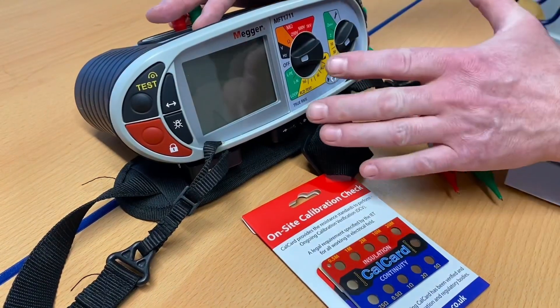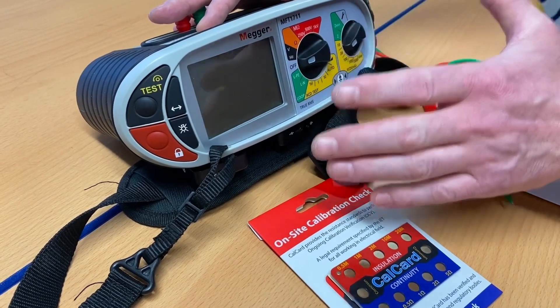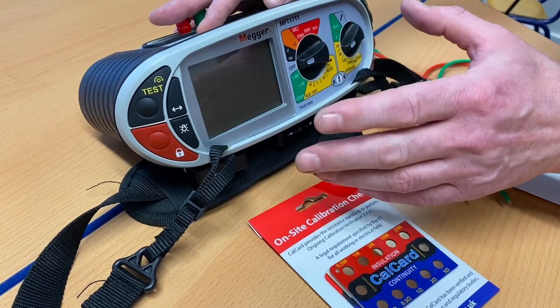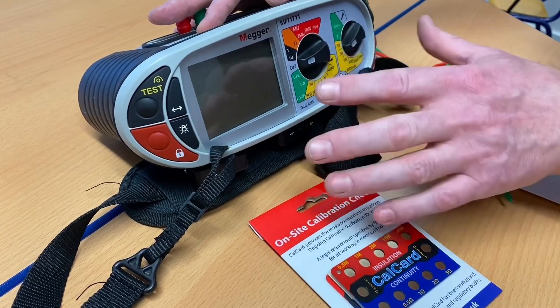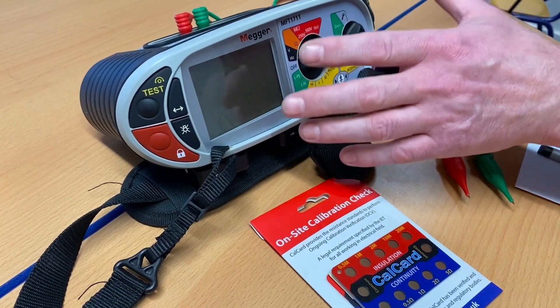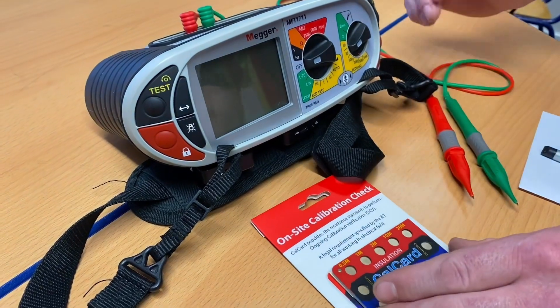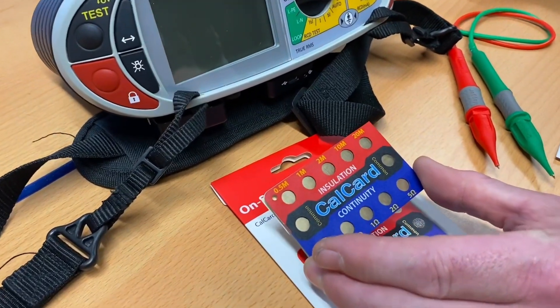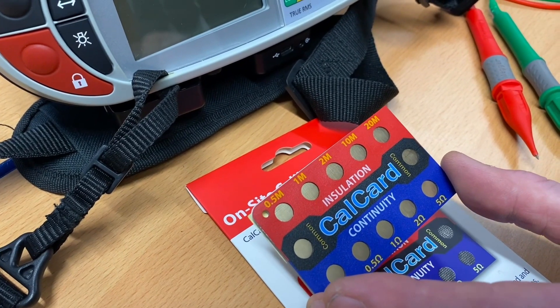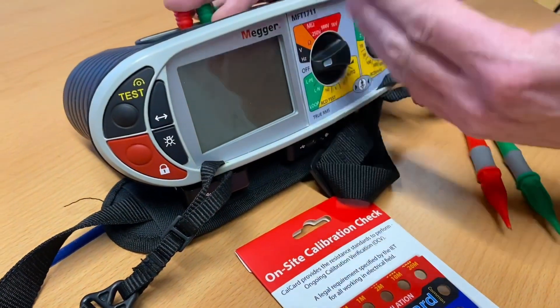In the electrical workshop, I like to confirm that our MFT testers are reading correctly for values of continuity measured in ohms and insulation resistance measured in mega ohms. In order to do that monthly, you should check your instrument out on site for all of the tests you can perform. However, this CalCard allows my students to confirm the readings are correct for the continuity and insulation resistance test.